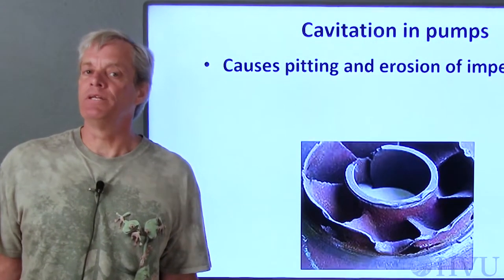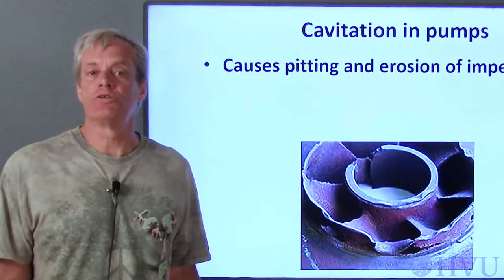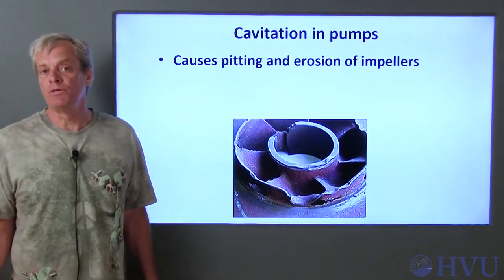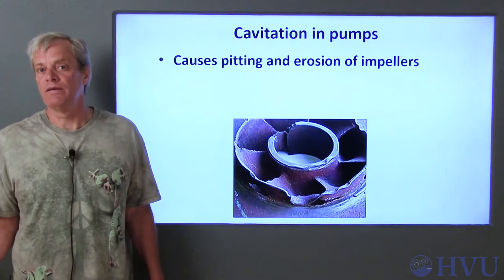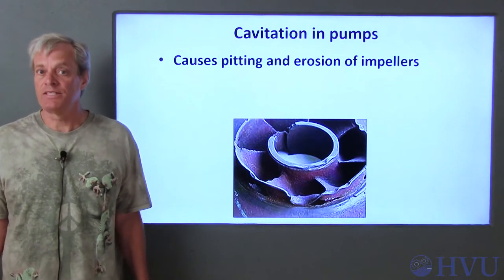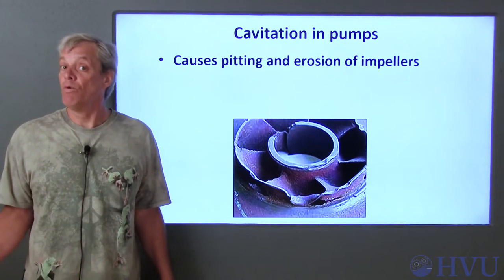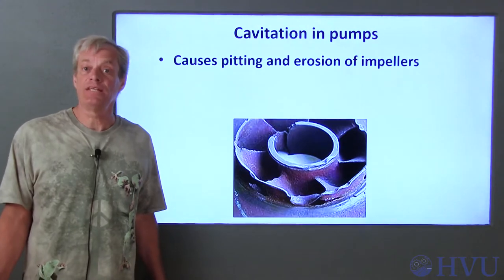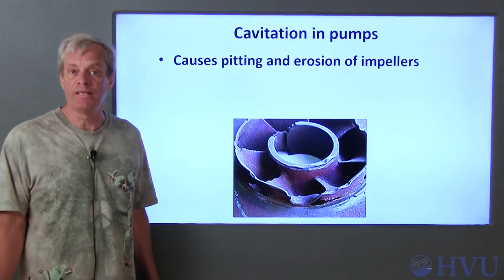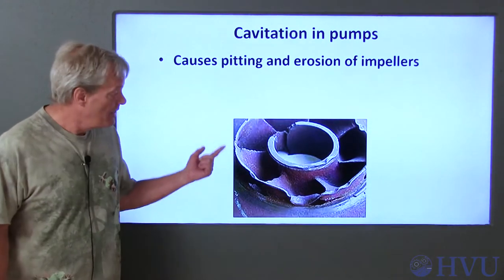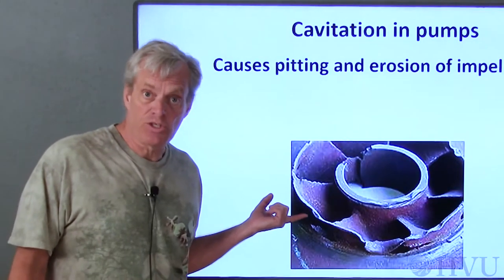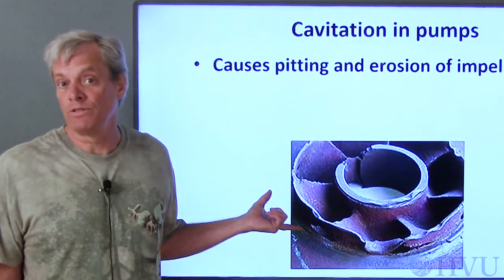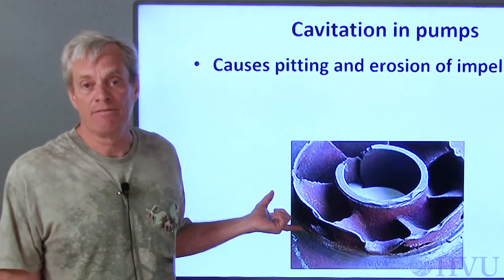Cavitation at pump inlets can be a major problem. If the cavitation bubbles form on the impeller blades, the pressure spikes created when the bubbles collapse can pit and erode the blades themselves. This is a picture of an impeller that's been pretty thoroughly chewed up by cavitation.